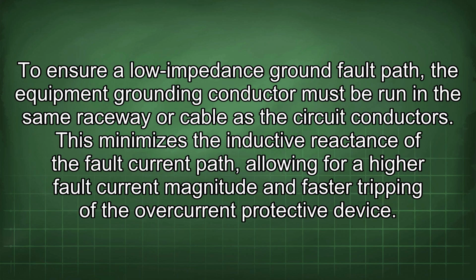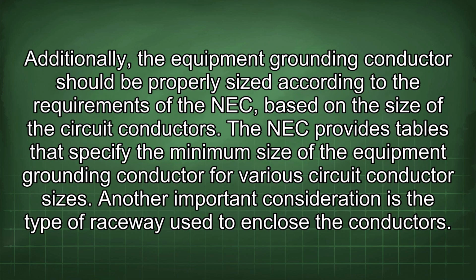To ensure a low impedance ground fault path, the equipment grounding conductor must be run in the same raceway or cable as the circuit conductors. This minimizes the inductive reactance of the fault current path, allowing for a higher fault current magnitude and faster tripping of the overcurrent protective device. Additionally, the equipment grounding conductor should be properly sized according to the requirements of the NEC based on the size of the circuit conductors. The NEC provides tables that specify the minimum size of the equipment grounding conductor for various circuit conductor sizes. Another important consideration is the type of raceway used to enclose the conductors.